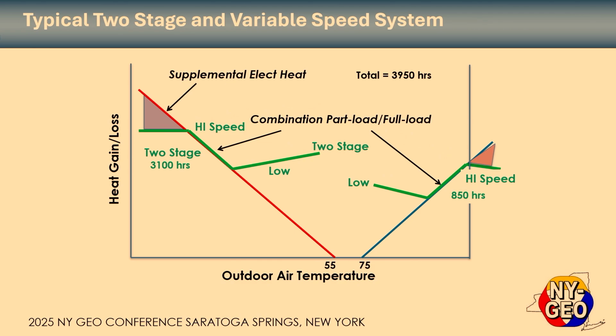As we get into higher technology, here's a two-stage equipment, which is more common today. And you can see the part load. So this would be like the low speed or first stage is a much lower capacity. And then, of course, when you hit that line, you're going to start bouncing between first and second stage, and you're going to track with the load until finally you're full 100% of the time on high speed. And, of course, then you still have that auxiliary that would need to kick in beyond that point. So finding out where that line is at is equally important on a two-stage, but you do track the load a lot more accurately with two-stage equipment.